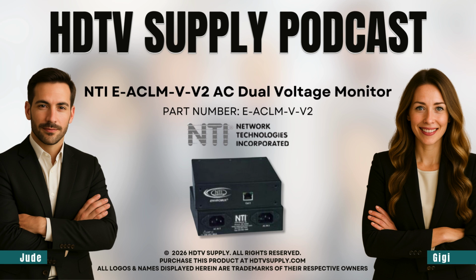And it reports back just two main things to the ENVIROMUX system. Which is like the central brain for all this environmental data. Precisely. It sends back the RMS AC voltage and the AC frequency, the hertz, and it's built to work globally, anywhere from 50 to 250 volts. Okay, so that dual monitoring alone really raises the bar for resilience.